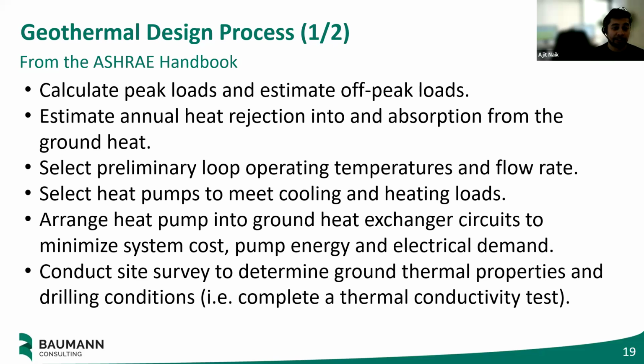I would never want to design a geothermal bore field with 500-foot wells, even if I took a bore of only 200 feet at my same location. Because I can't extrapolate what's happening between 200 and 500 feet under the ground with just a 200 feet bore, even if it's on my site.